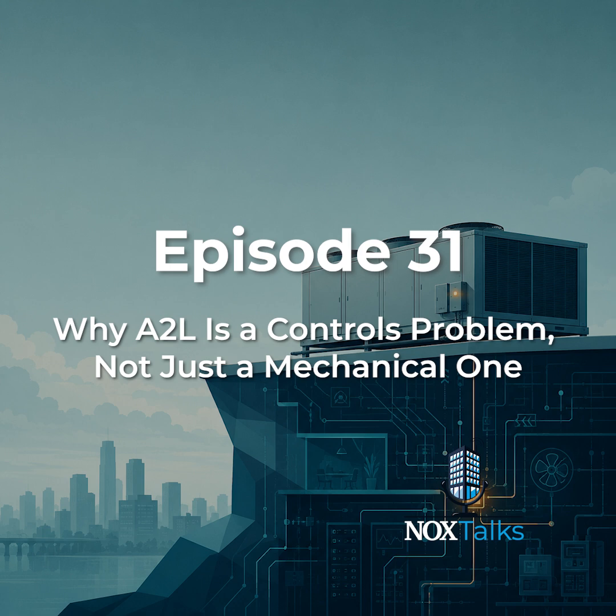Second, budget the controls integration now, not at install. If there's external coordination work, points, programming, commissioning that safety sequence, it's its own cost. And finding it late means a scramble and probably a change order. And third, track the compliance dates, but don't carve them in stone. Because EPA has recently reconsidered and amended pieces of the program, go by the current EPA table, not an old summary.